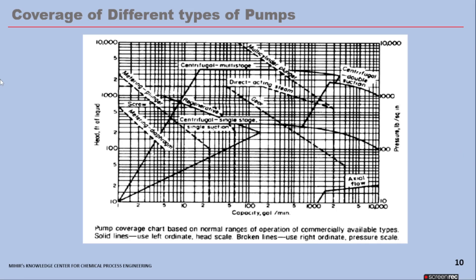Here we see the pump coverage chart based on normal ranges of operation of commercially available types. The vertical axis shows head in feet of liquid, and the horizontal axis shows capacity in gallons per minute. Solid lines use the left ordinate (head scale); broken lines use the right ordinate (pressure scale in PSI). In the lower capacity, high-pressure range, you can see metering diaphragm pumps and metering plunger pumps — very high PSI values. Centrifugal pumps appear in the middle of the range. Gear pumps have higher capacity and can also reach high pressures. Axial flow pumps are at very low head but very high capacity.